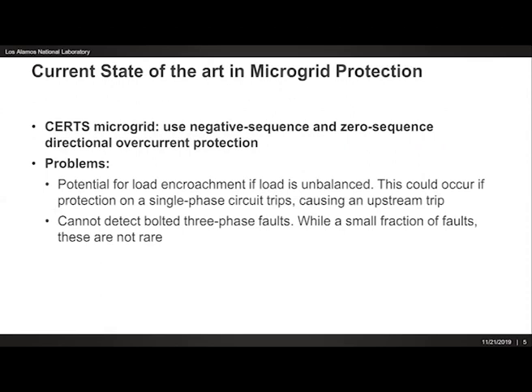So again, going back to what's happening in industry these days, they're generally still using overcurrent protection. They rely on negative sequence and zero sequence protection, which can work if loads are close to balanced. However, if we have a lot of loads that are single phase circuits, such as residential or office loads, and we have a fault on one of the single phase circuits, we can lose that, increase the unbalance of the system, and this could trip the negative sequence or zero sequence protection erroneously. So it's not an ideal solution.